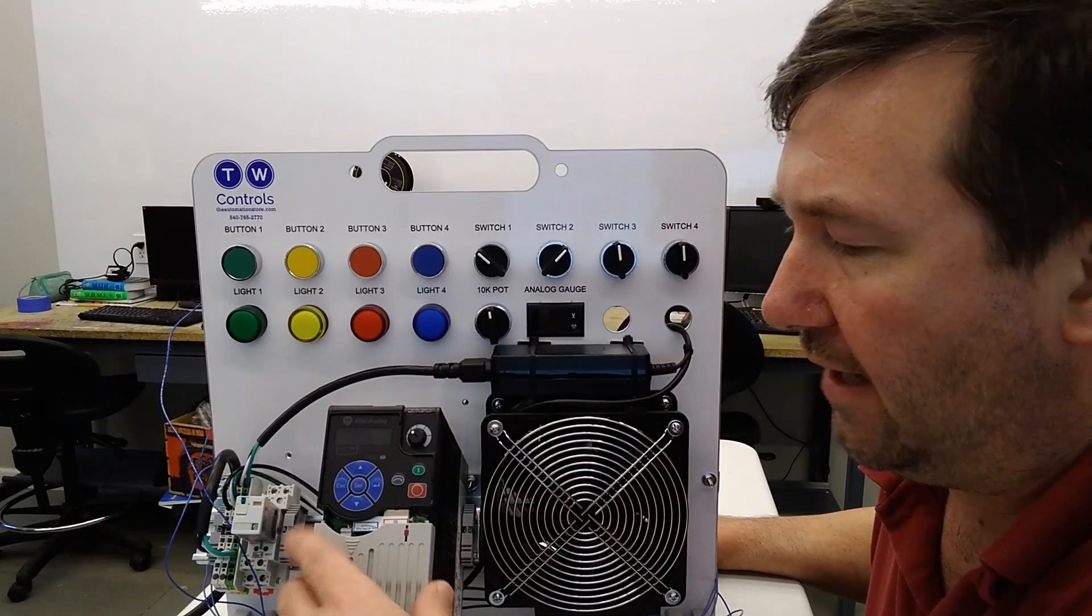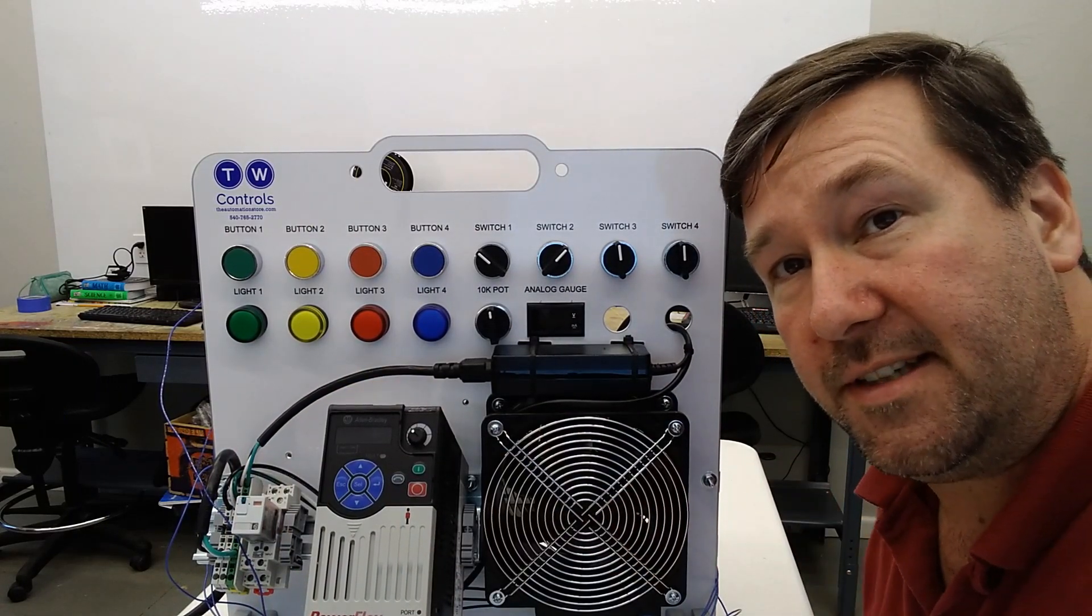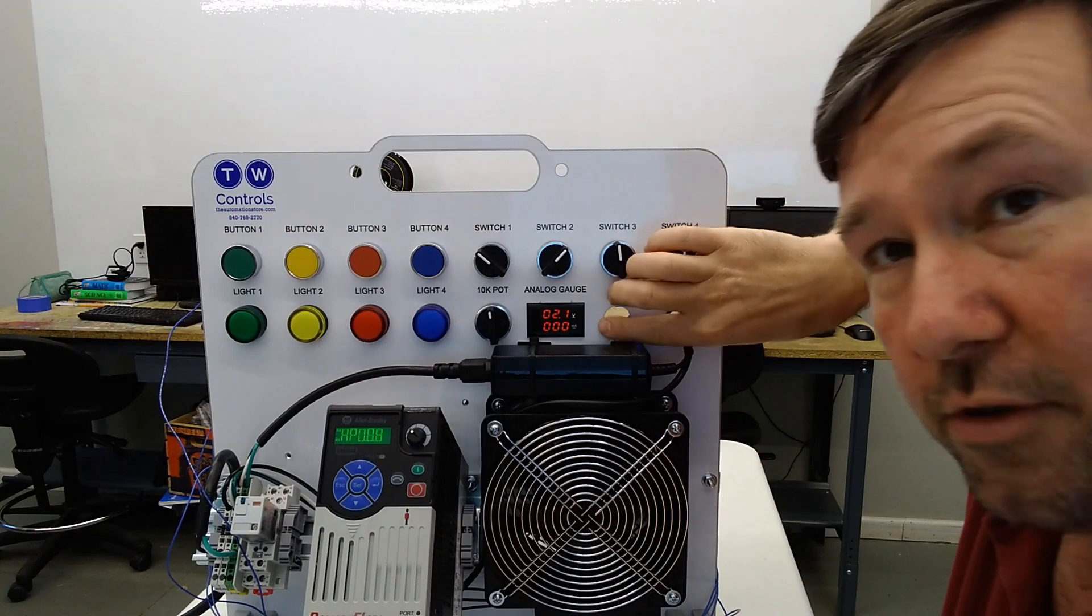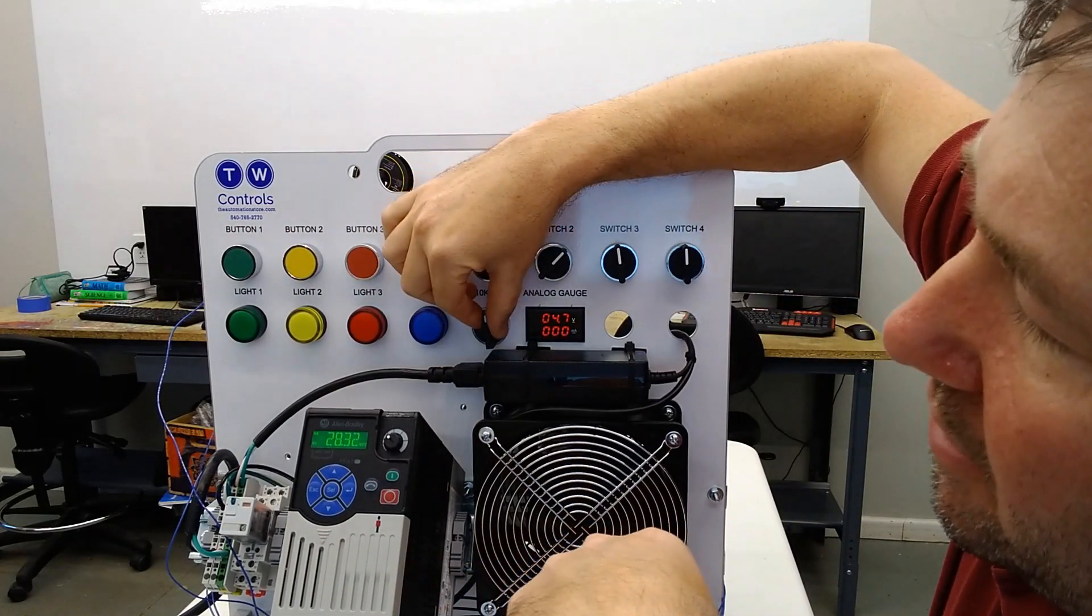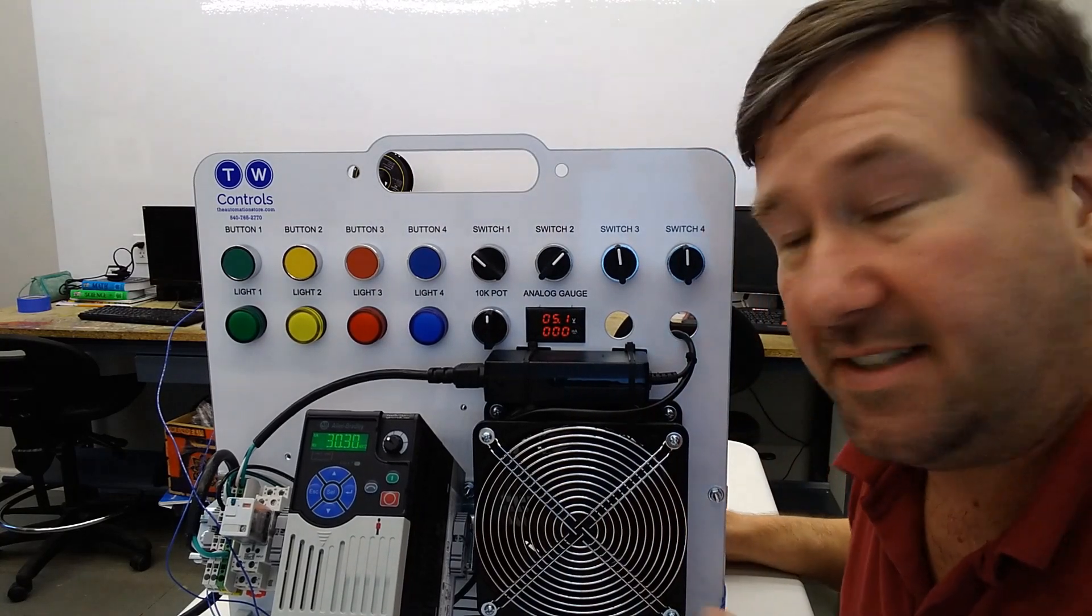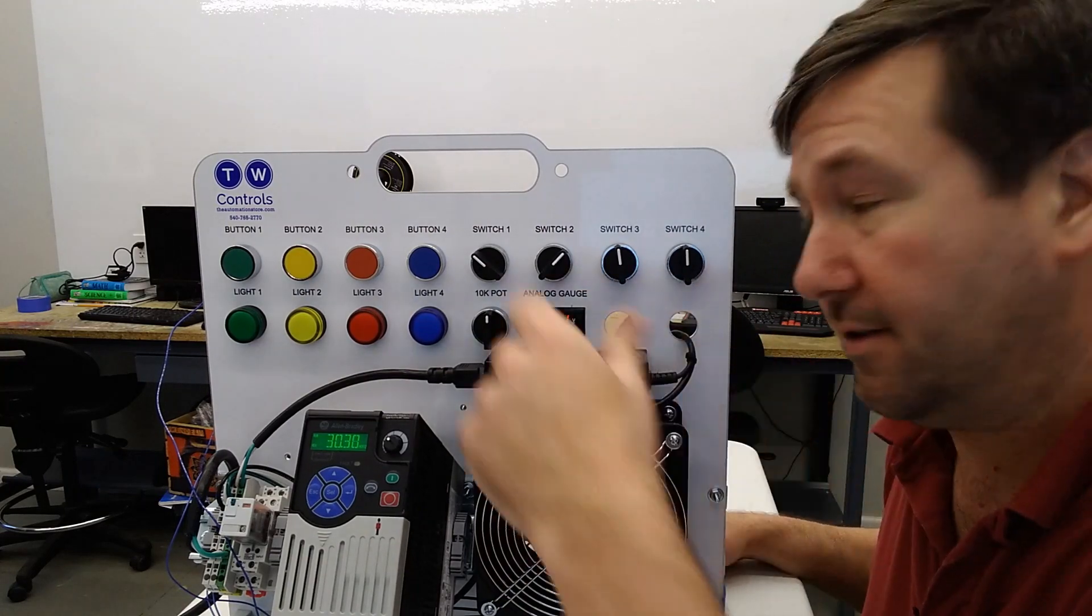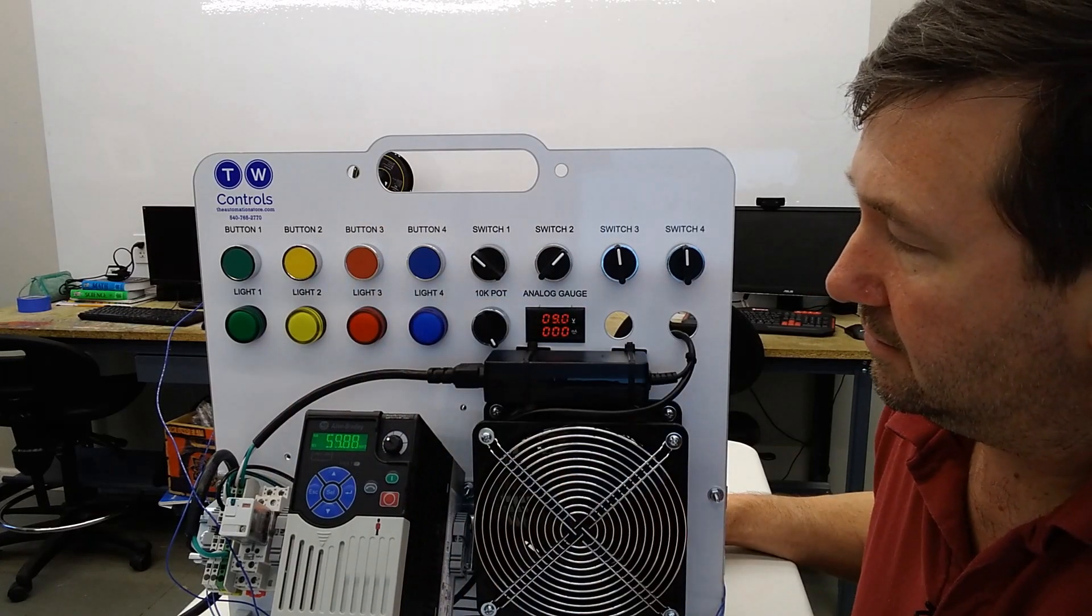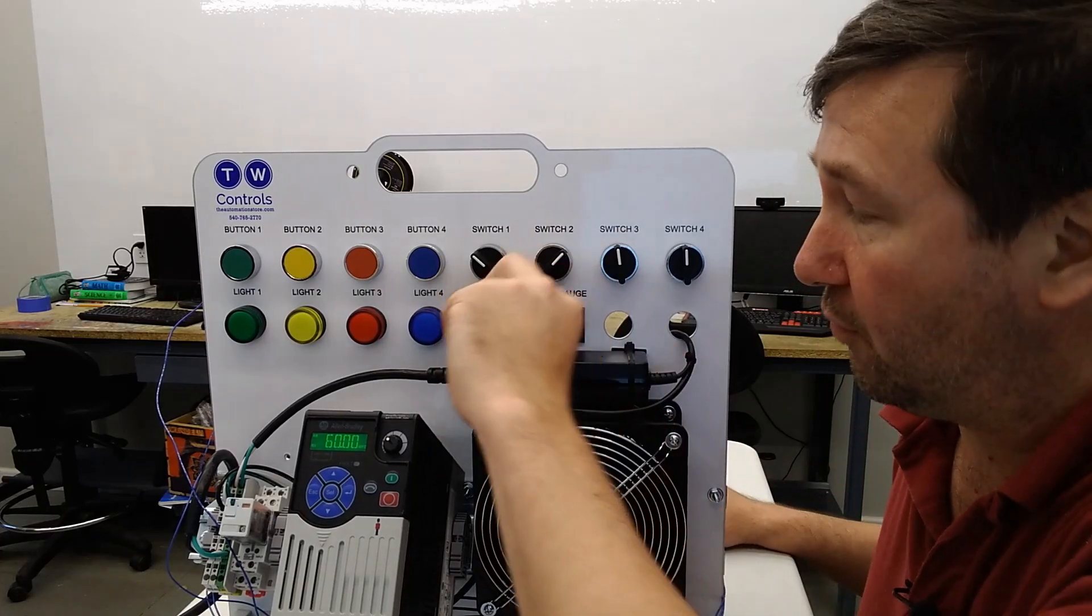The default analog output is the output frequency. So let's go ahead and power it up and see what it does. We'll press our green start button. All right, and our voltage is coming up. We're at about 28 hertz. In fact, let's bring this to about 30 hertz and that should be right at about five volts, which is exactly what we have. Now I'm going to turn it on up and I apologize in advance for the noise on the mic. But just to show you, if we turn it wide open, we're going to end up at 10 volts or the maximum output frequency.